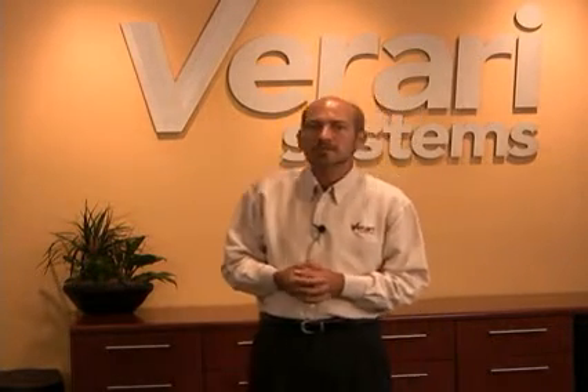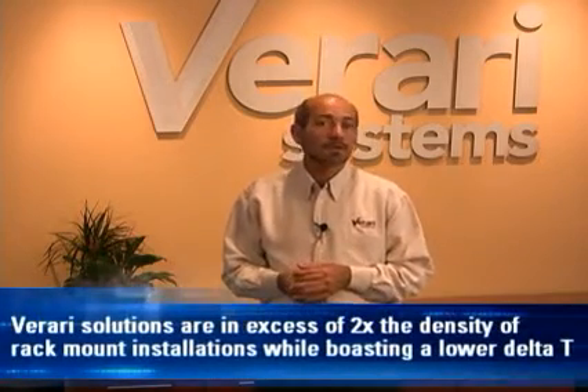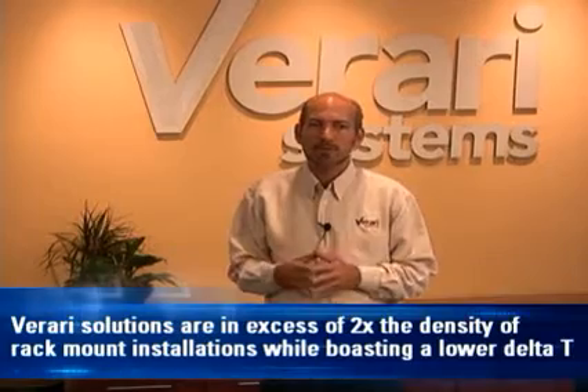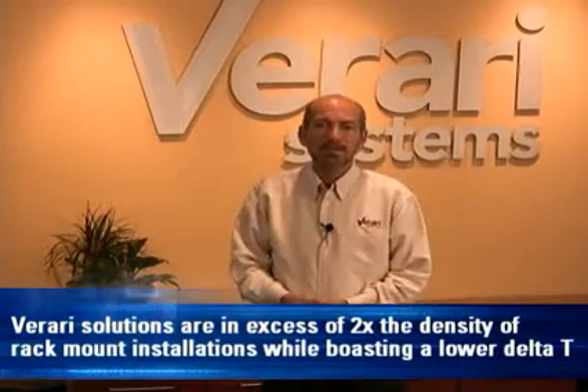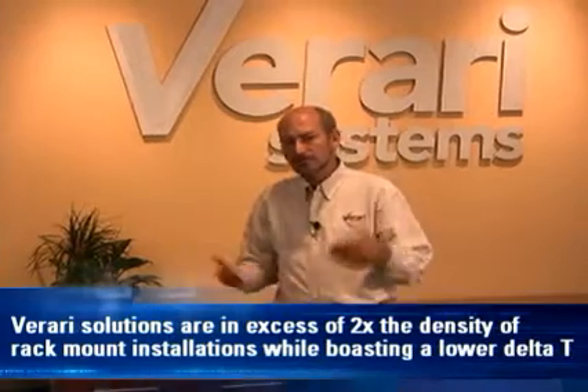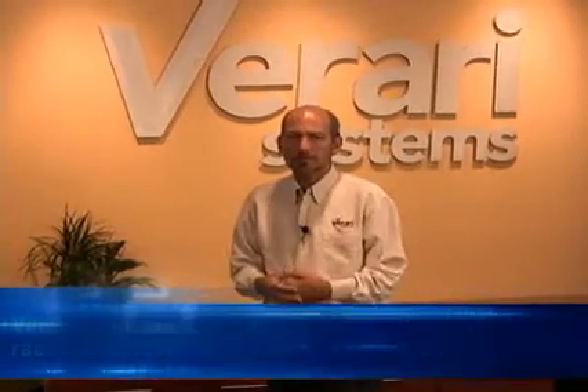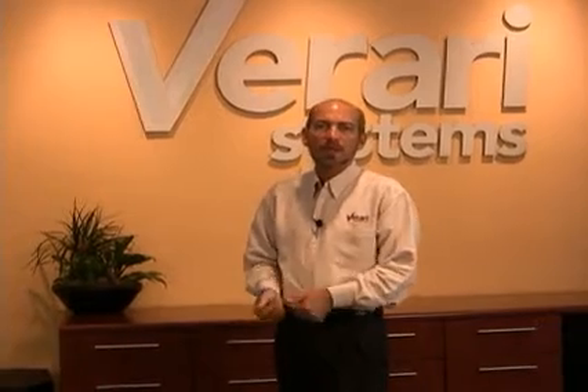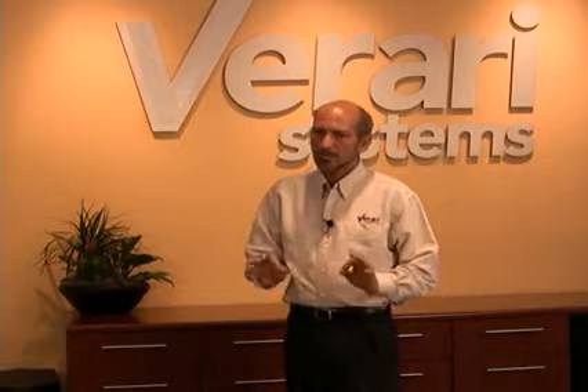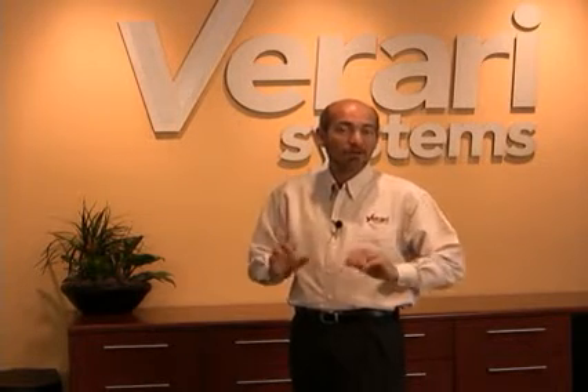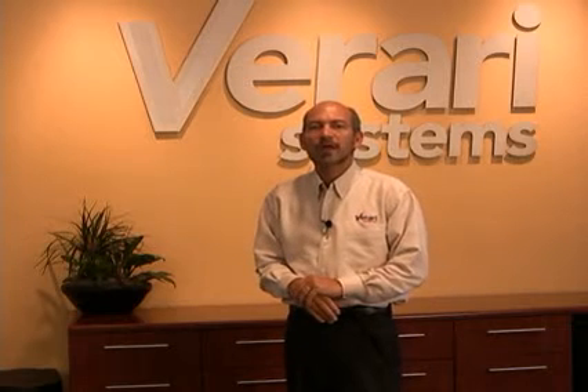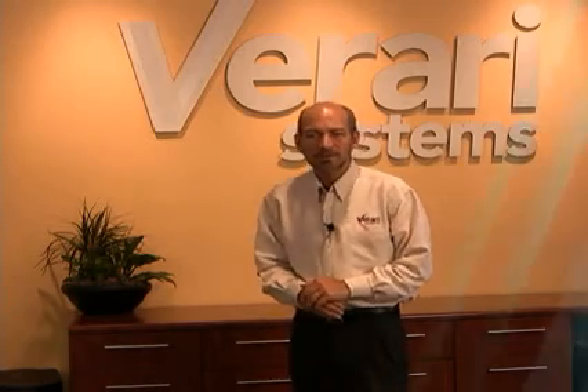configuration. Even when you have more machines, our blade architecture is in excess of 2 times the density of your typical rack mount, and yet we have a lower delta T. And the delta T is fully controllable based upon the fact that we can control the fan speed. If you're in a data center where you've got a very heavy load and you need to increase the volume, we're capable of controlling the fan speed, increasing it, enabling the system to draw more air to it. If you're in a data center where the airflow is necessary to keep it low and you've got a lighter load, you can speed down the fans and set them to a point where you're using just the least amount of air possible to keep your delta T where you'd like it to be.